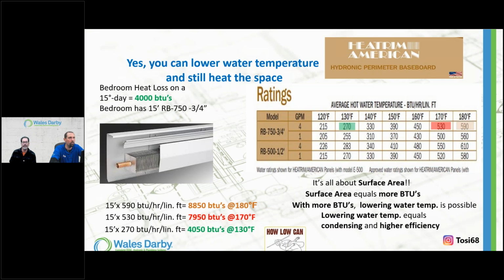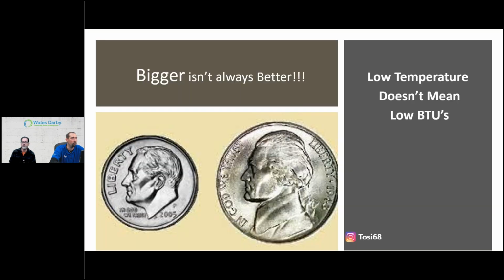Design day is key, but we're so rarely there. We're so rarely at that extreme of cold, right? Can we get there? Can we get colder? Yes, you can. So bigger isn't always better, right? And the value of the dime versus the nickel, it's so powerful as a visual to see that. I'd rather have a stack of dimes than a stack of nickels. Bigger isn't always better. Low water temperature doesn't mean low BTUs.